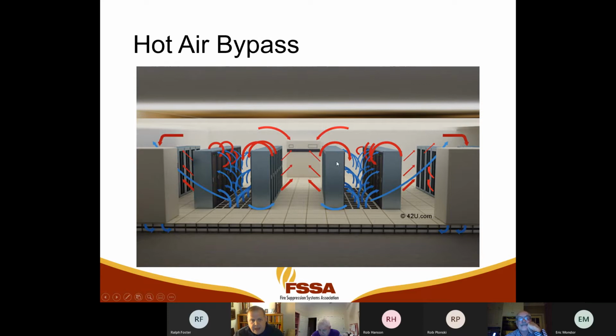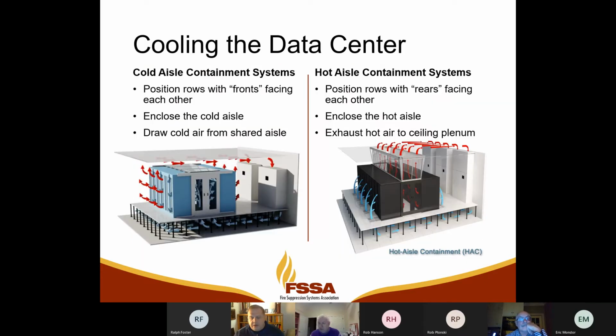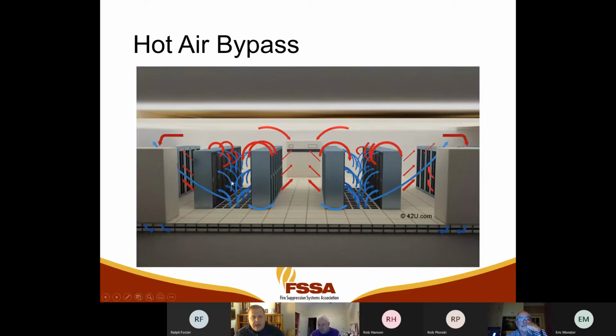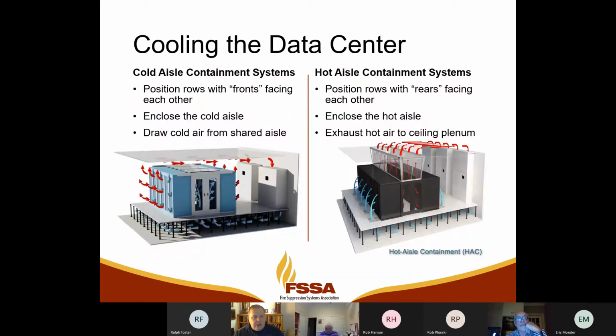There will be some bypass, and that bypass reduces the efficiency of the cooling method and can lead to overheated IT equipment. And IT equipment that runs too hot doesn't necessarily perform its computing duty as well. So operators are starting to want to avoid this bypass condition as air volume and air exchange rates have gone up, and rack densities have gone up. So they go to aisle containment systems, and this is ultimately where we're going to spend our time talking about the rest of this presentation and the challenges with it.